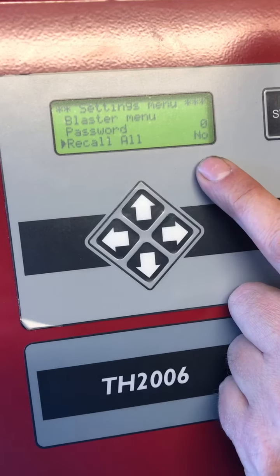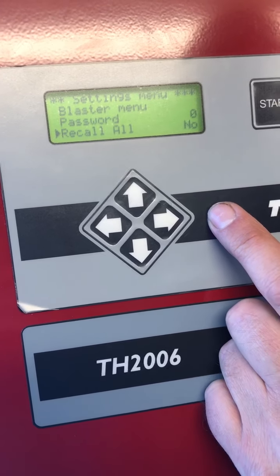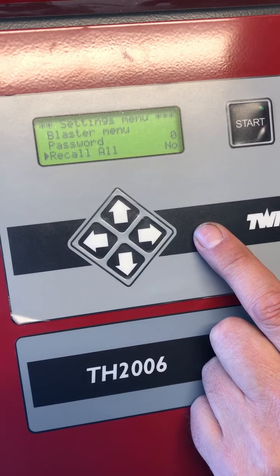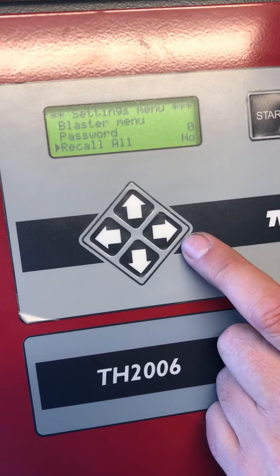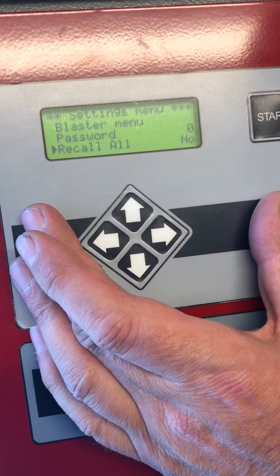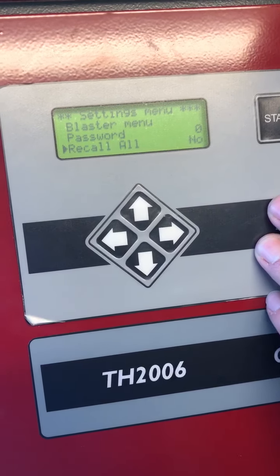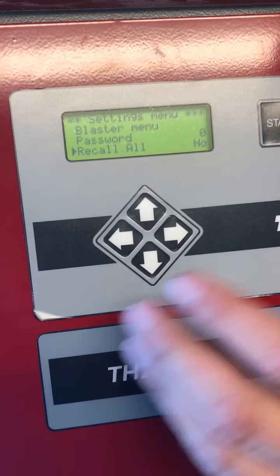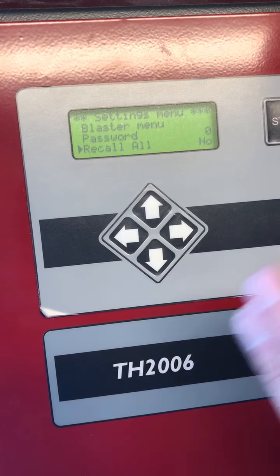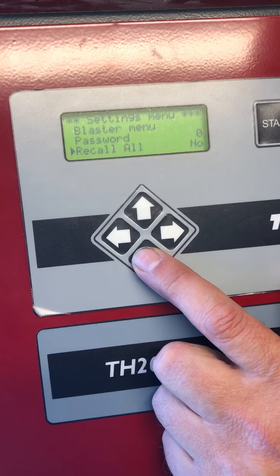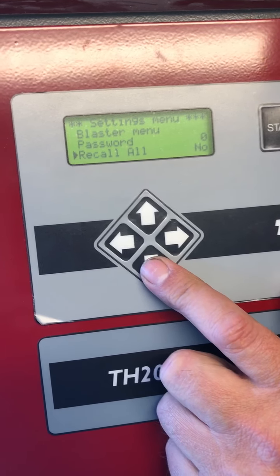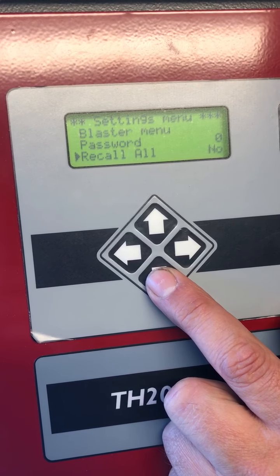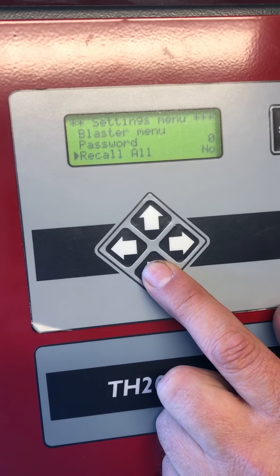Here we have one called 'recall all'. It doesn't recall all, but it does recall some of the settings. If we want to make a full recall, we go into this unit — which is a CS150 — go into password 82, change it to a CS250, go back again, change it back to CS150, and it's back to the factory menu again. But then remember you have to test and put in again the weigh-in menu on the different fuels and adjust and calibrate the lambda probe.